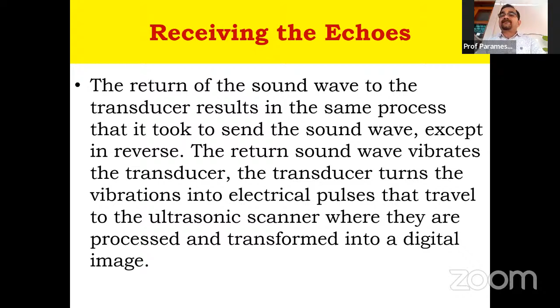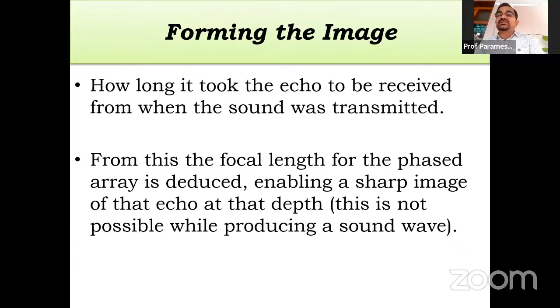So this is the transmission, then the reception, and the composite beam which has been used in this. Next. Number 3 is forming an image. How long it takes for the echo to be received from when the sound was transmitted; from this, the focal length for the phased array is deduced, enabling a sharp image of that echo at that depth. This is not possible while producing a sound wave.